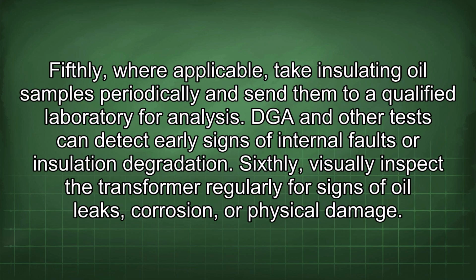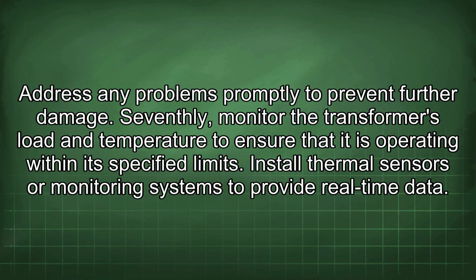Fifthly, where applicable, take insulating oil samples periodically and send them to a qualified laboratory for analysis. DGA and other tests can detect early signs of internal faults or insulation degradation. Sixthly, visually inspect the transformer regularly for signs of oil leaks, corrosion, or physical damage. Address any problems promptly to prevent further damage.